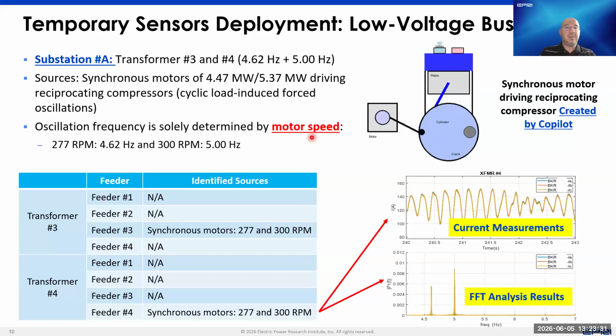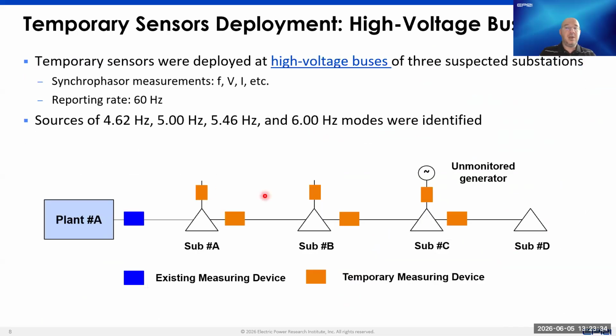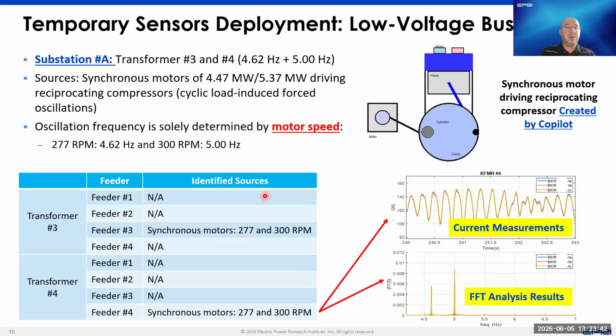Specifically for substation A, they got permission, and in collaboration and with support from the industrial load customer, they were able to install or deploy temporary sensors at the low voltage side. So in this case, we were able to go even deeper into the system to try to identify what equipment is creating those oscillations. After we installed those sensors at the low voltage buses, we confirmed and validated that the source of those oscillations were the synchronous motors connected at those substations.